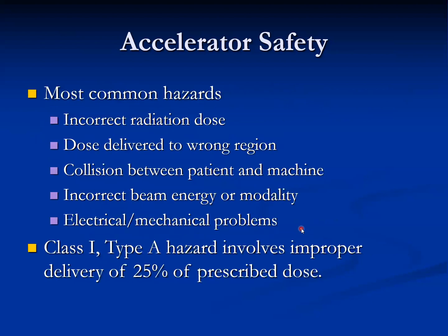The most common hazards are incorrect radiation dose, dose delivered to the wrong region, collision between patient and machine, incorrect beam energy or modality, and electrical and mechanical problems. Class I, Type A hazard involves improper delivery of 25% or more of the prescribed dose.